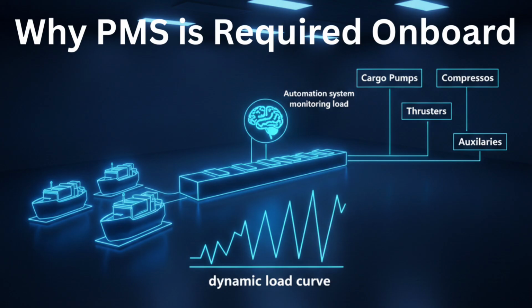Without an automatic management system, sudden load increases can overload generators, causing trips and potential blackouts. Sudden load decreases can make generators inefficient, wasting fuel and increasing wear. The PMS constantly monitors the system, starting or stopping generators automatically, shedding non-essential loads, and balancing load sharing. This ensures essential systems remain powered, voltage and frequency are stable, and blackouts are prevented. This automation significantly reduces human error, improves safety, and enhances operational efficiency.